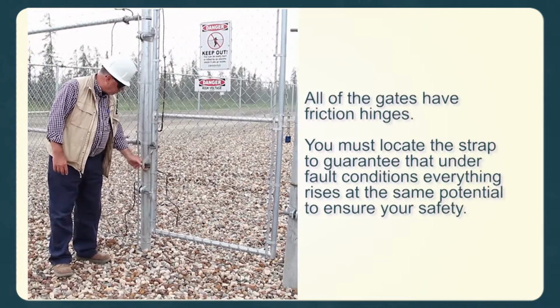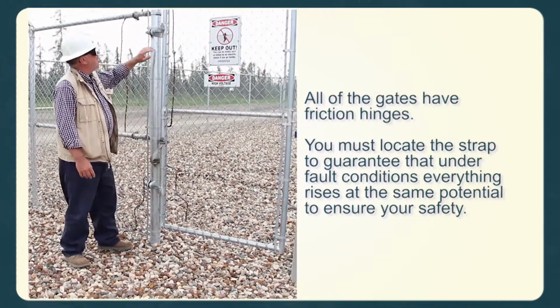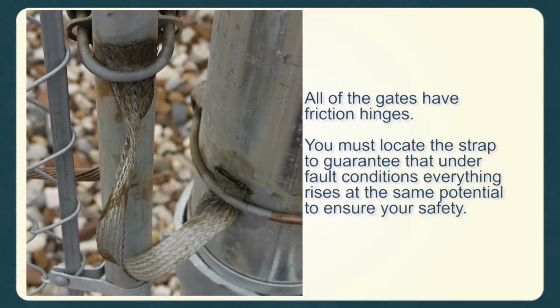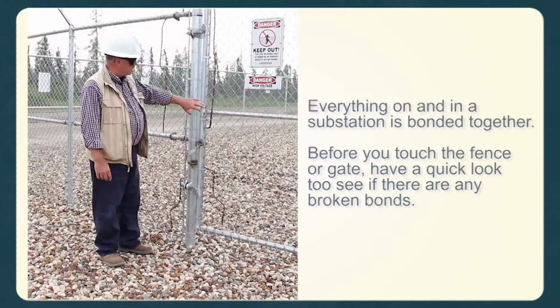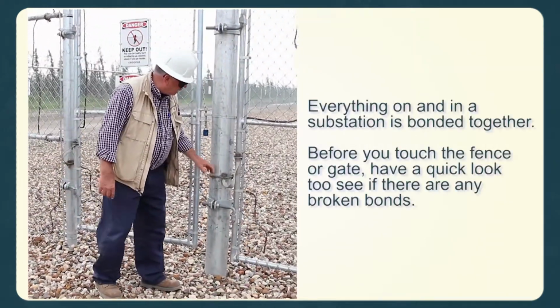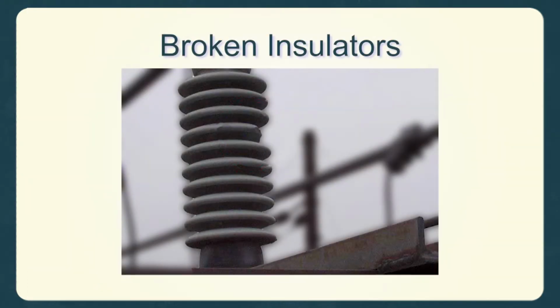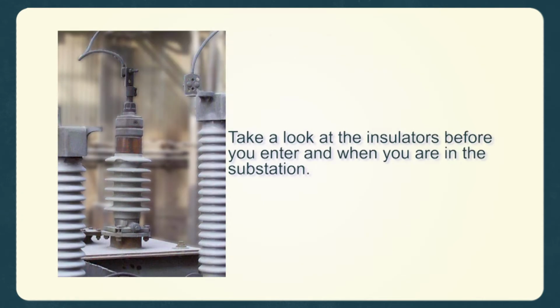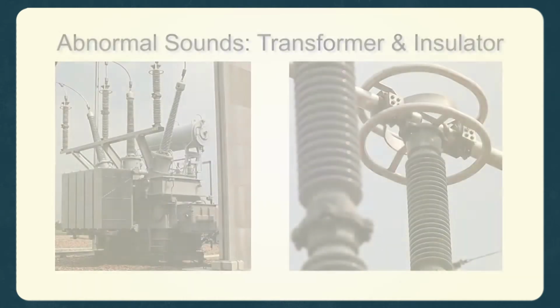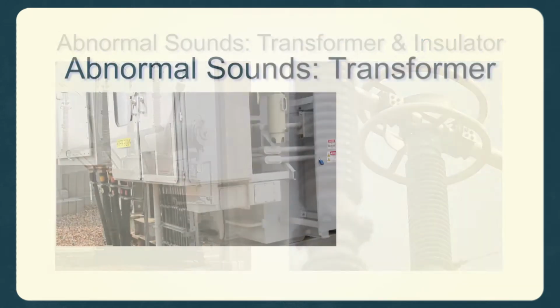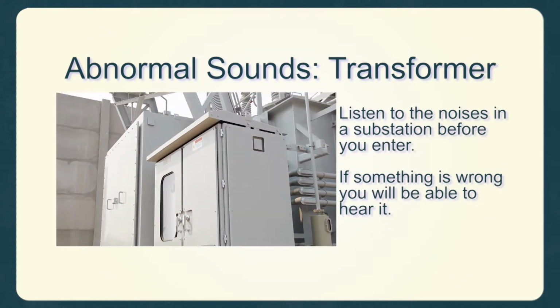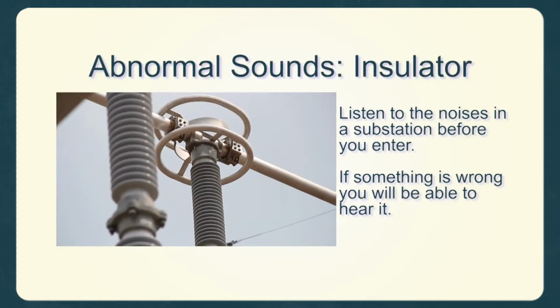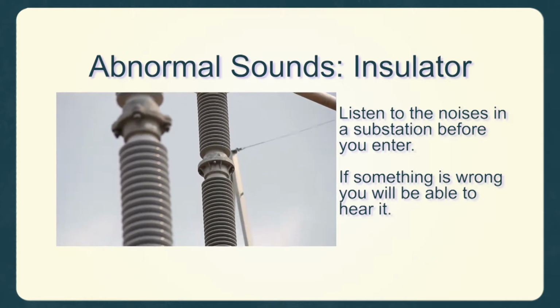You're also looking for the strap. These hinges here are friction hinges. They need a strap, so under fault conditions, everything rises at the same potential. You can see the ground. It's everywhere. Everything is bonded in. Broken insulators. Take a look at the insulators before you enter and when you are in the substation. Abnormal sounds, transformer and insulator. Listen to the noises in a substation before you enter. If something is wrong, you will be able to hear it.